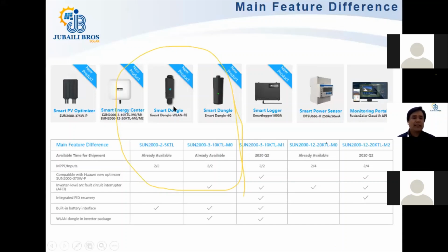The dongle comes free with the 3 to 10 KTL; you need to buy the 4G one separately. The Smartlogger is 1000A, which we have in stock, but newer versions are the 3000A and 3000B. The smart power sensor needed for zero export is also available with Huawei, coming with a current transformer that can measure up to 250 ampere, usable for PV systems up to 170 kilowatt requiring zero export.